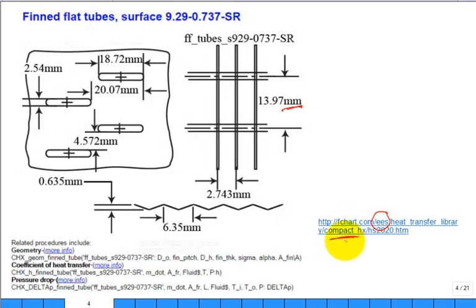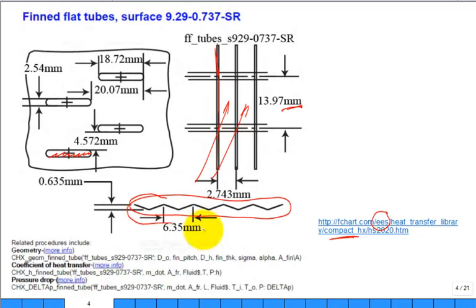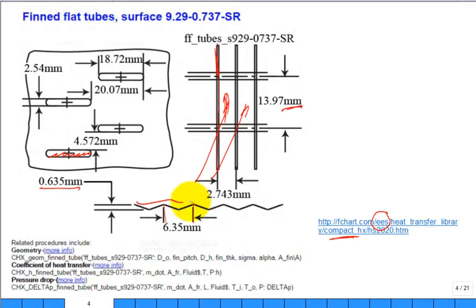This illustration shows the flat tube passages where the water flows, the fins between them, and the cross-flow direction for air. The fin isn't straight — it has kinks, promoting heat transfer. The data table provides fin pitch: 9.29 fins per inch. The fin metal thickness is 0.004 inch, and it's copper as stated in the problem.